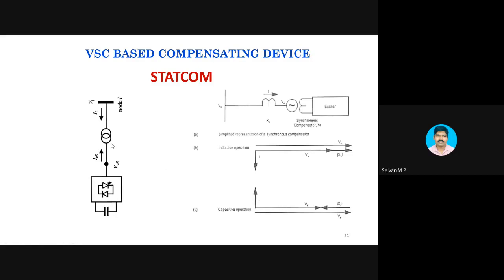Actually, though you have a VSC, if you connect this VSC directly to this node, then nothing will happen. Actually, the power electronics is playing the role, but the power electronics alone cannot do this job. If you do not have this transformer or a reactance, which we may call a coupling reactance, you cannot achieve this. You will not find any paper or book which connects this device directly to this bus, because this voltage and this voltage will become the same when you directly connect it. When these two voltages are instantaneously the same, there cannot be any reactive power flow. That's why you need a reactance in between.